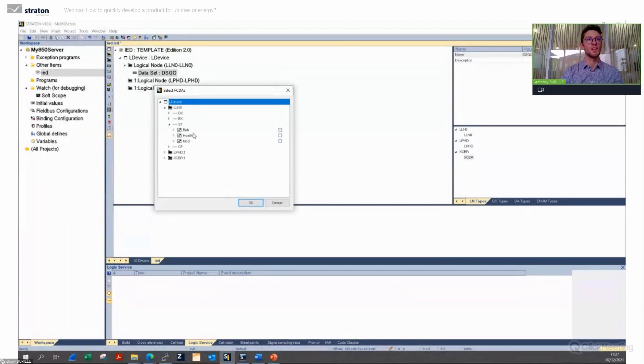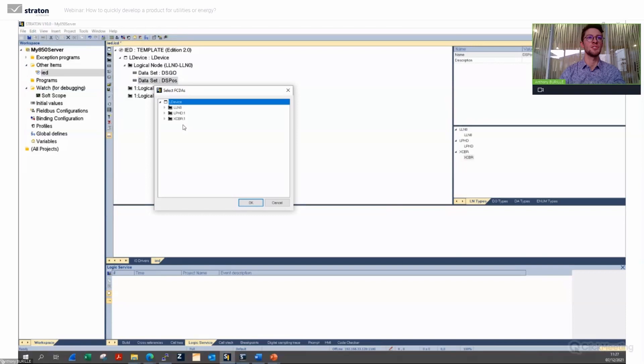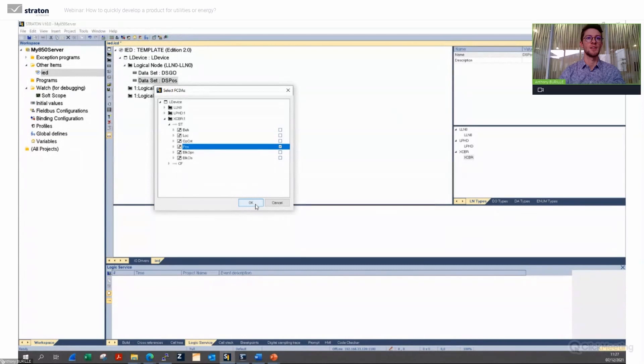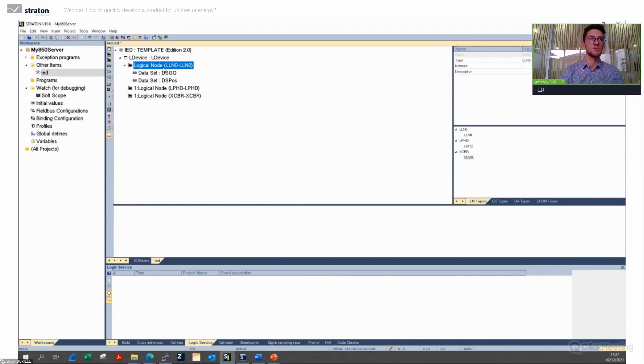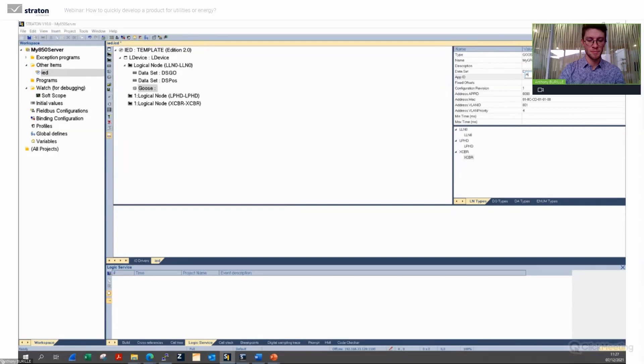We click OK and we want to communicate the logical device health to other substations using GOOSE. First I create a new dataset — I'll call it DS_GO for the GOOSE dataset. I double click on it and choose to communicate Logical Node 0 health over GOOSE. We also want to communicate the circuit breaker position to an 61850 client, so I create a new dataset called Position, double click on it, go to circuit breaker position, check it. Now I have to configure report control blocks using this dataset, so I create a GOOSE control block.